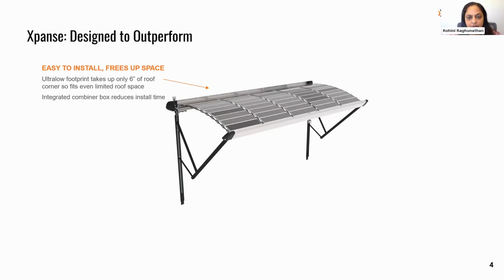We even have an integrated combiner box—this is our proprietary combiner box right here. It combines all the strings that come out of the PV box, and it's already mounted into the mounting rail. So the installer really just brings 2 6-gauge wires. It's designed with the installer in mind to make it easy.